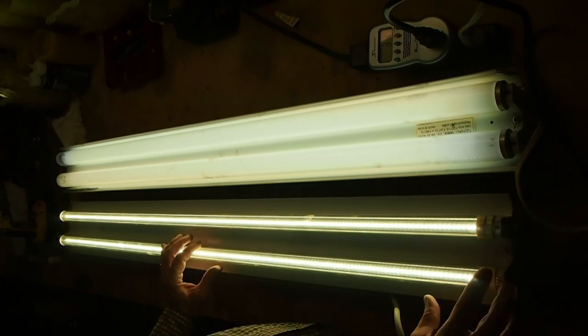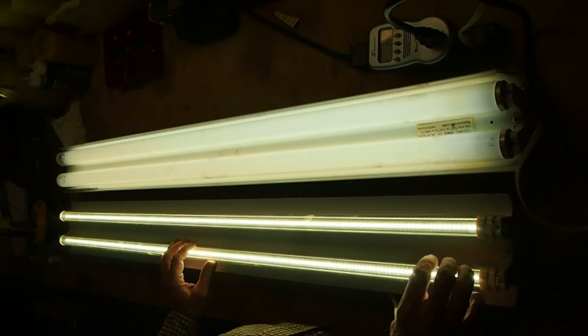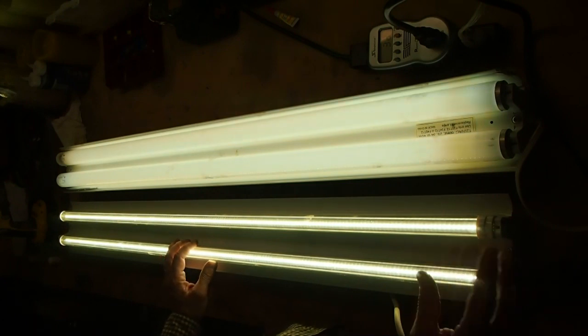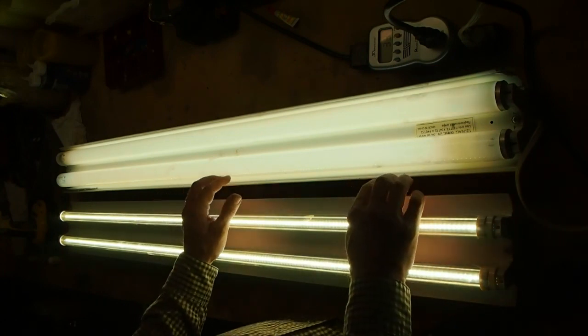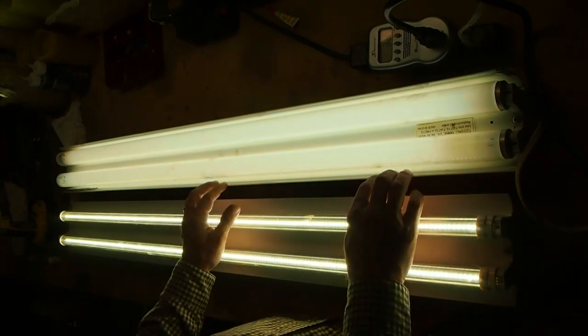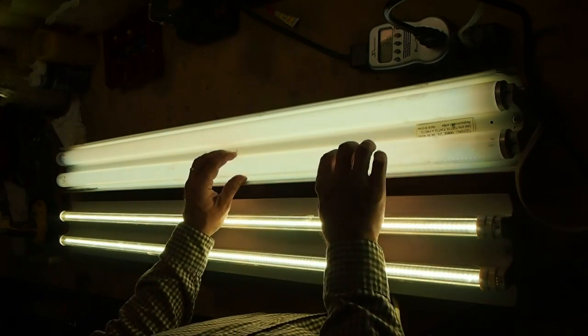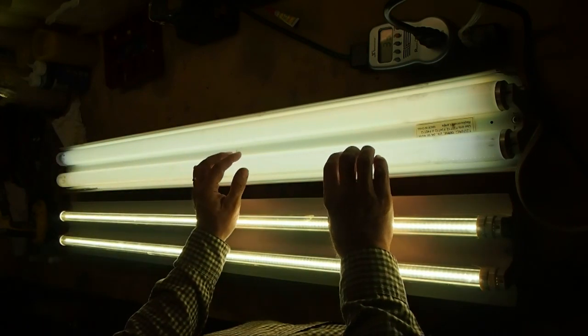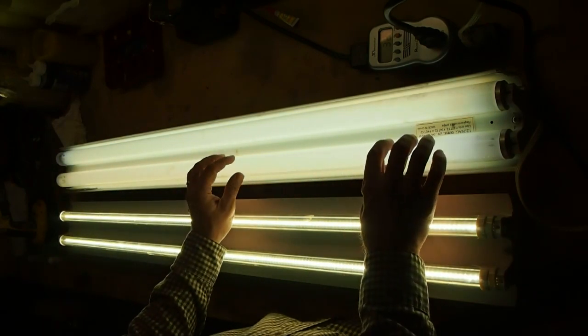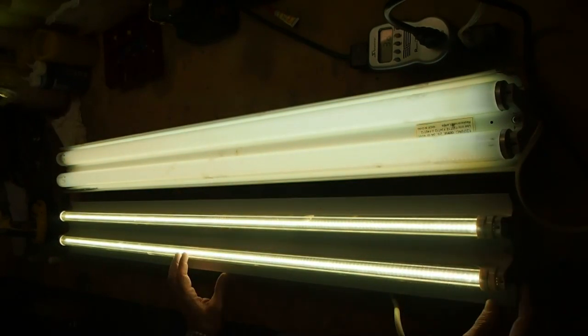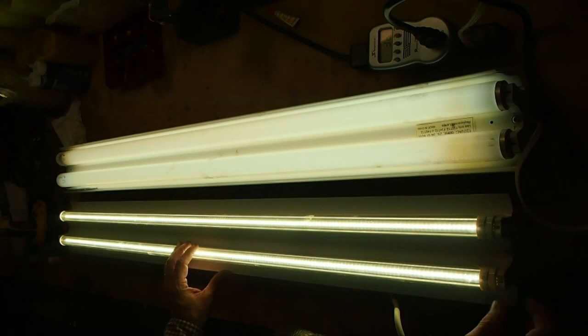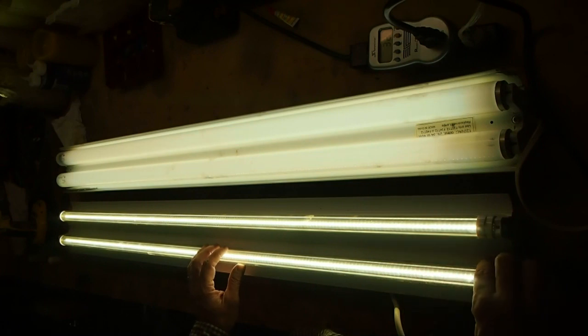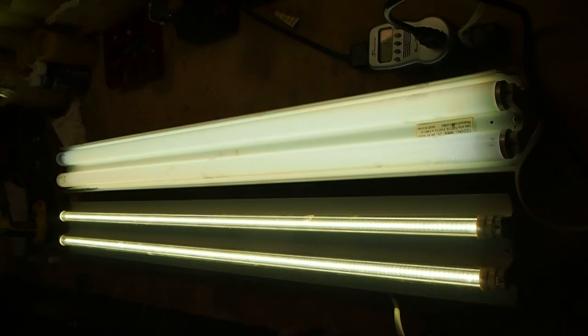So, for me, really the most compelling reason to upgrade to these LED bulbs is not for the energy savings. I would say it's primarily because of all the stuff that we took out of that fixture. We took out the ballast. If there was a starter, we took that out. And for me, I've never had great luck with fluorescent tubes. These things are rated at 12,000 hours, but I'm constantly replacing these. They go dim, they start flickering, and they drive me crazy. So, I'm really looking for the LED bulb not so much for its power efficiency as for its long-term reliability. These bulbs are rated at 50,000 hours, so you're basically talking about a lifetime bulb, assuming they never go out.